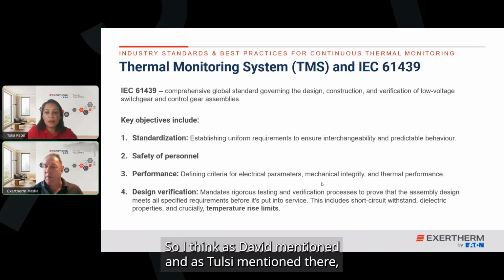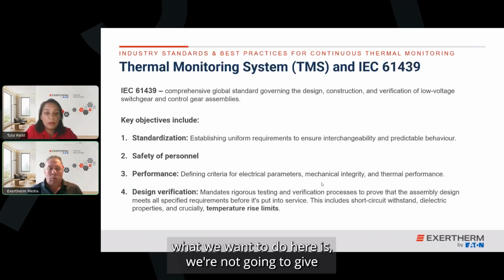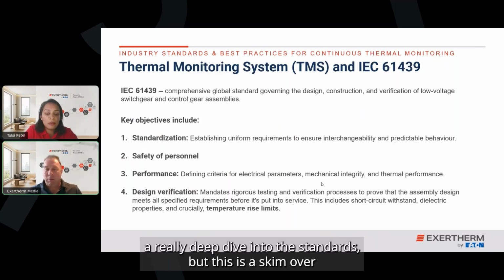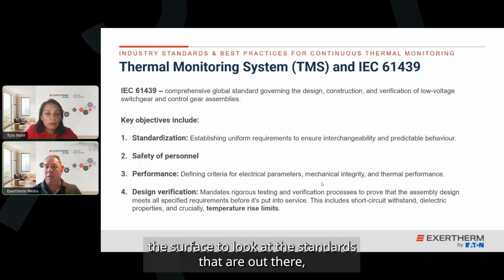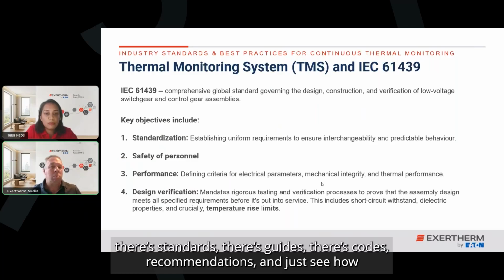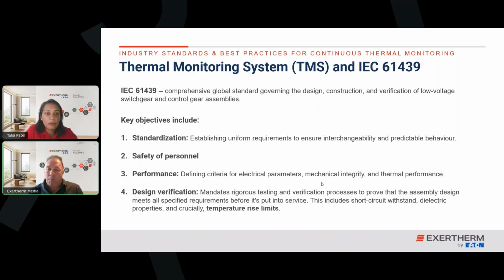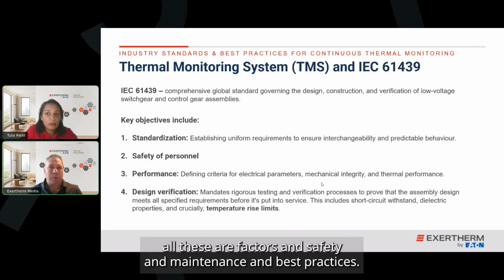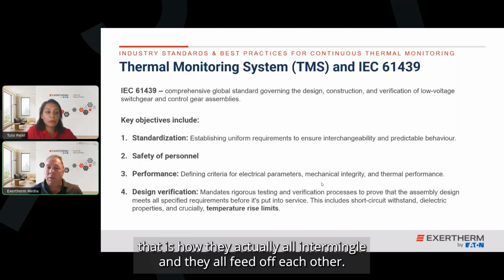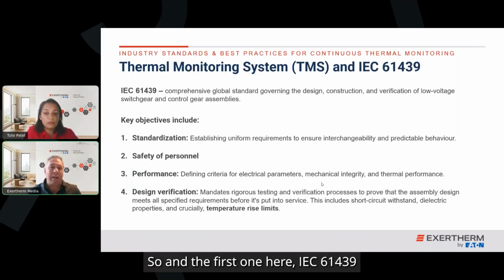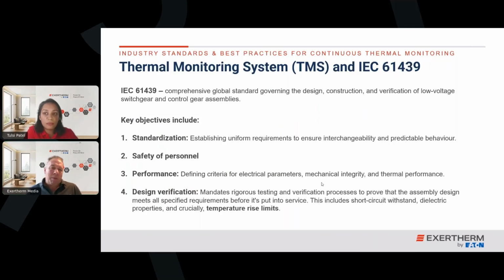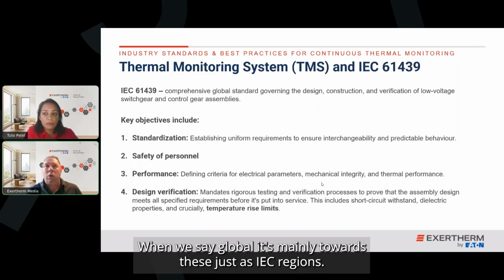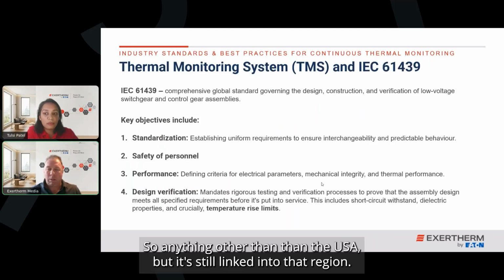So I think as David mentioned and as Tulsi's mentioned there, what we want to do here is we're not going to give a really deep dive into the standards, but this is a skim over the surface to look at the standards that are out there. There's the standards, there's guides, there's codes, there's recommendations, and just see how all these affect us in safety, in maintenance, in best practices. And again, as Tulsi mentioned, how they actually all intermingle and they all feed off each other. So the first one here, IEC 61439, it's quite a global standard. When we say global, it's mainly towards the, as it says, IEC region, so anything other than the USA, but it's still linked into that region.